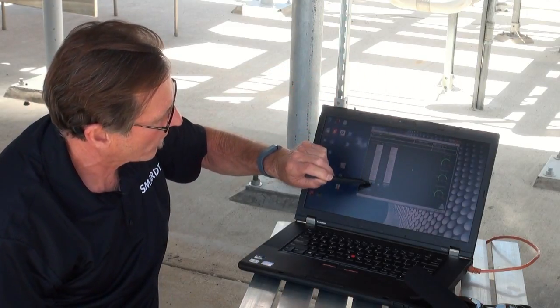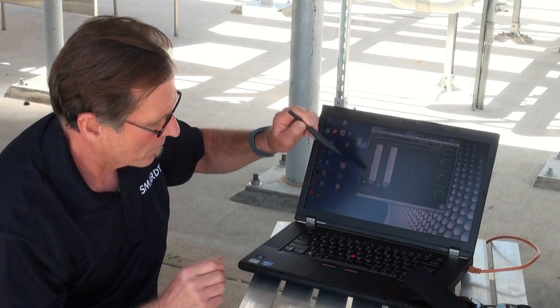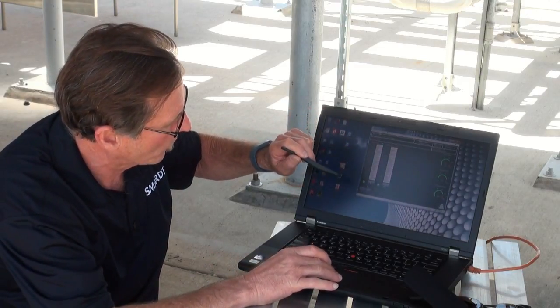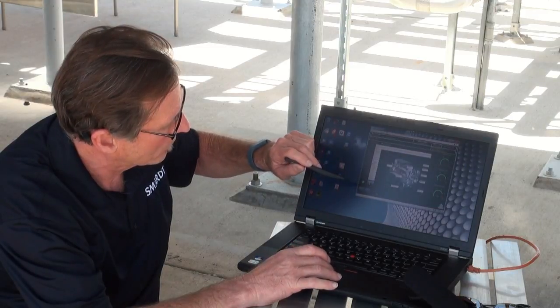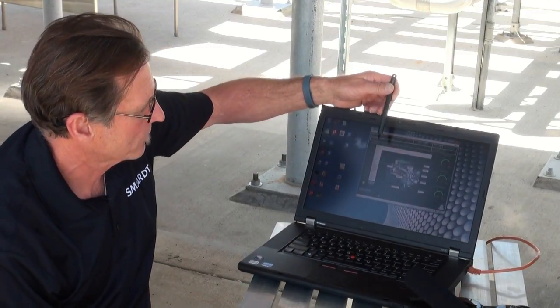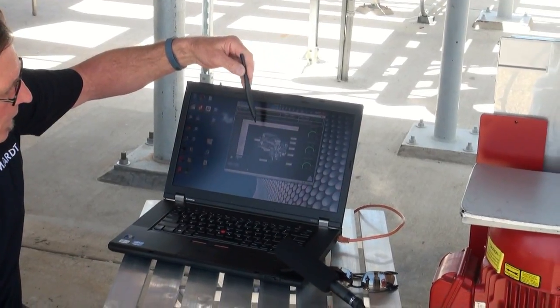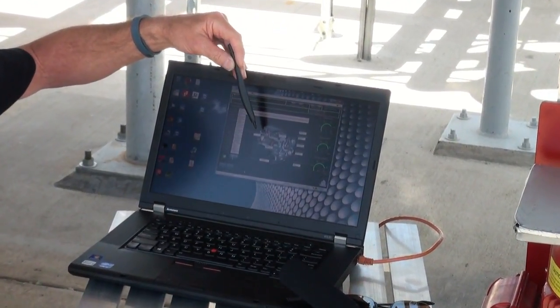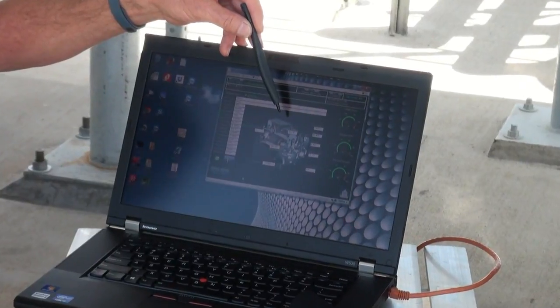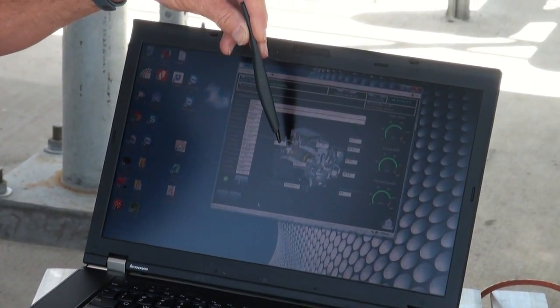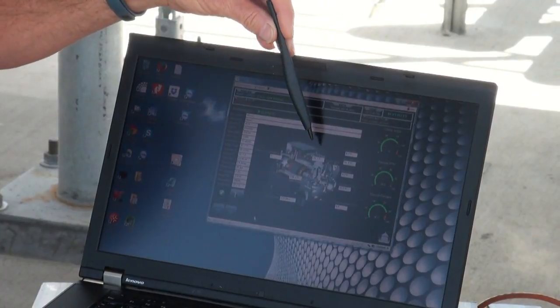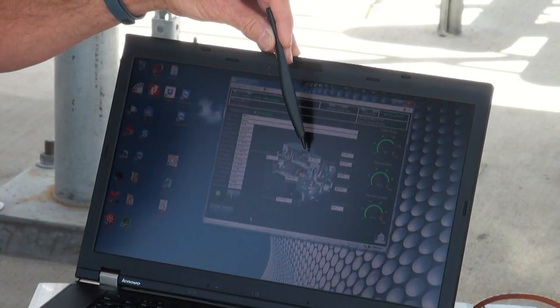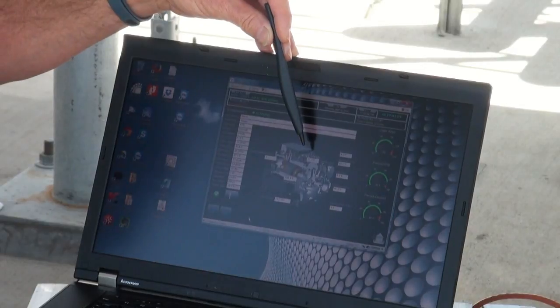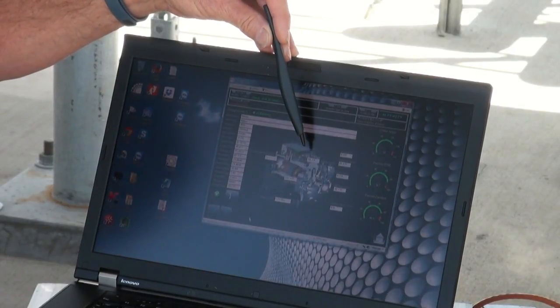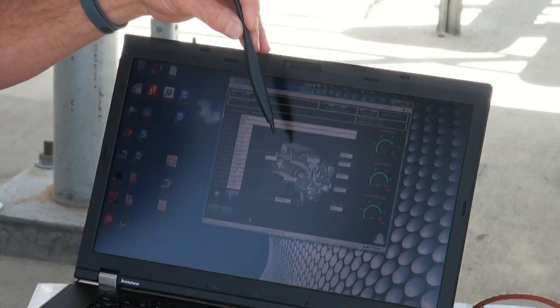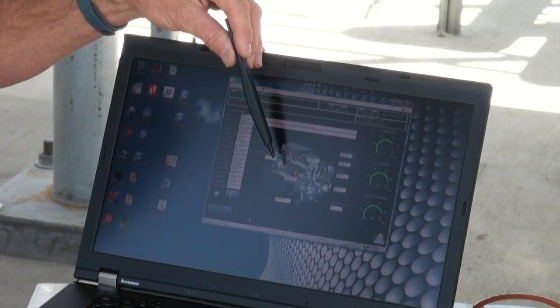But then you can open up compressor 1. You click the number 1 here, and you get an expanded view of the compressor. Gives you even more information. What to look for here would be our cavity temperature, which is running at 106, and our inverter temperature, which is 77. That's our drive, our inverter. So right now it's running at 78 degrees, which is pretty much normal. And our cavity temperature is 107, which is normal as well.